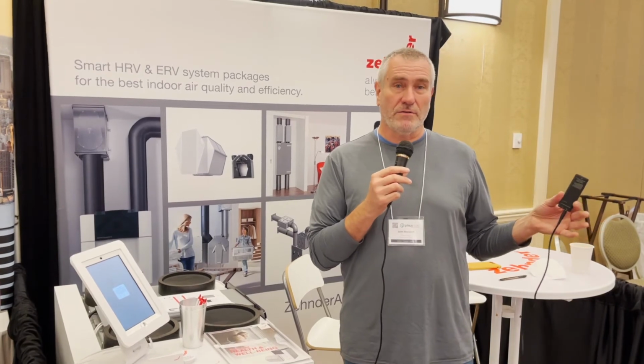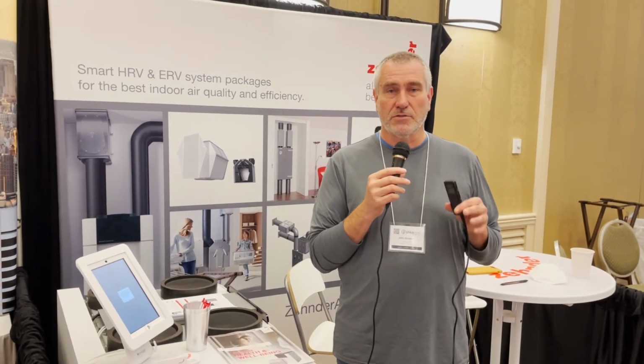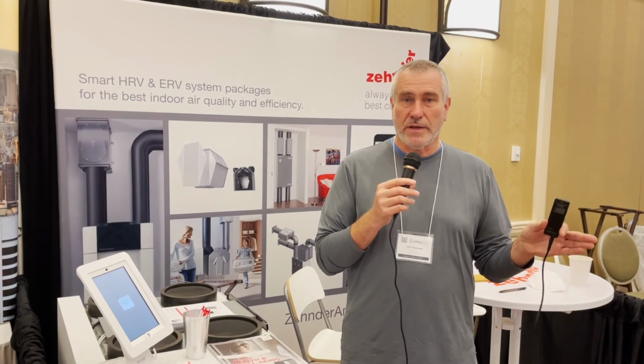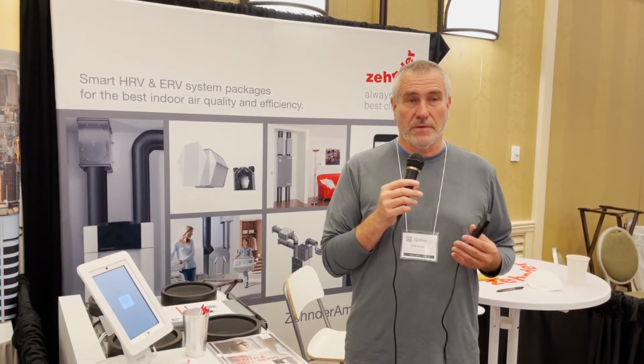Similarly, the ductwork for heating and cooling is a lot bigger than what you need for ventilation, so why not size the ductwork appropriately? We offer a home run system with 3-inch UL-listed tubing that can fit between joist bays and stud cavities, making for a very convenient installation — even in retrofit solutions, the soffits don't need to be nearly as big.